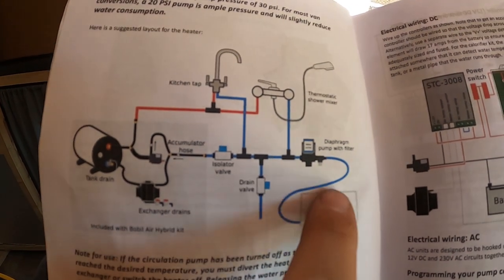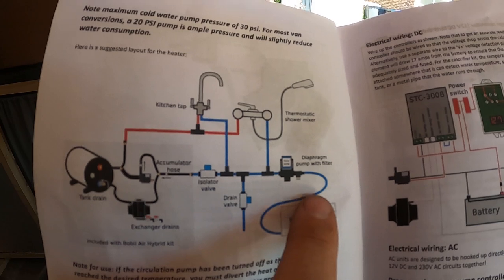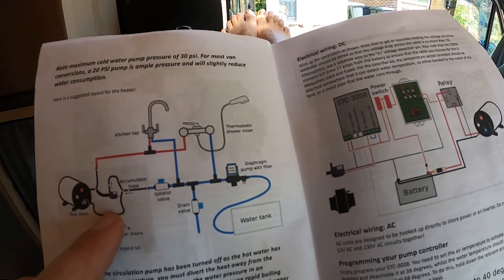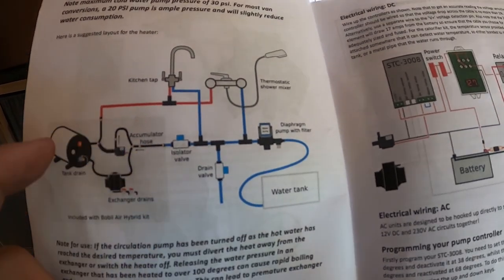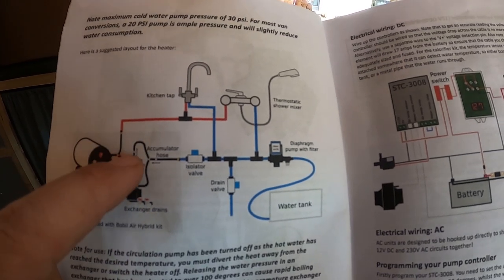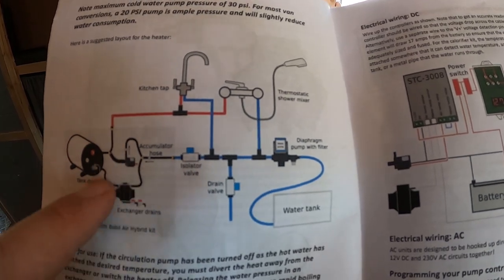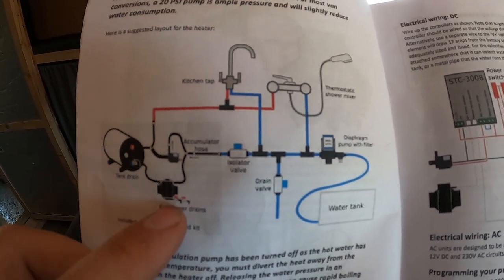Water tank to pump — the cold water goes to the pump and then goes to your shower or kitchen tap. The cold carries on into here. So the water — this pump's going this way, and there's a one-way valve there, so I was just confused about why the water coming out of this pump and out of the heater wouldn't go the wrong way. But yeah, there's a one-way valve. The water will circulate using this little pump, circulating water through the heat exchanger and through the 12 volt element. If the heat exchanger isn't on, the 12 volt element does the warming up instead.